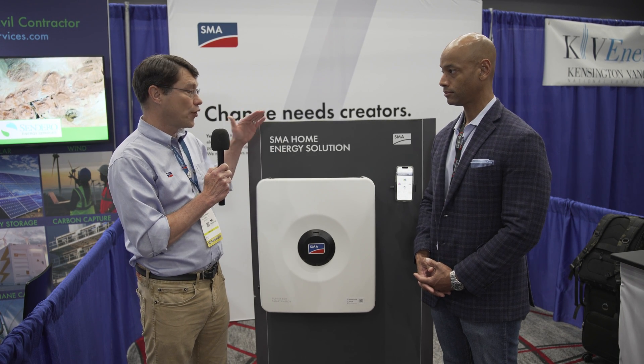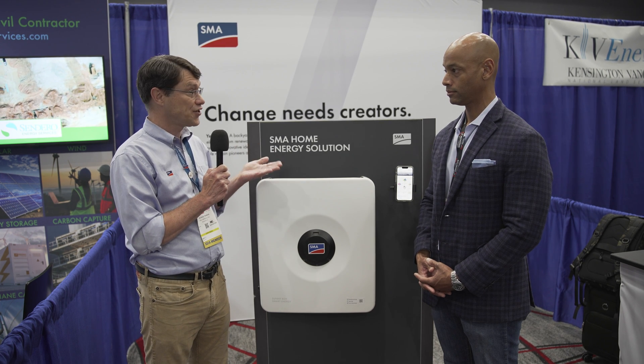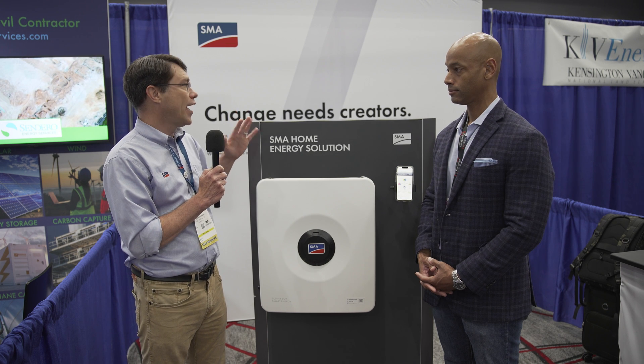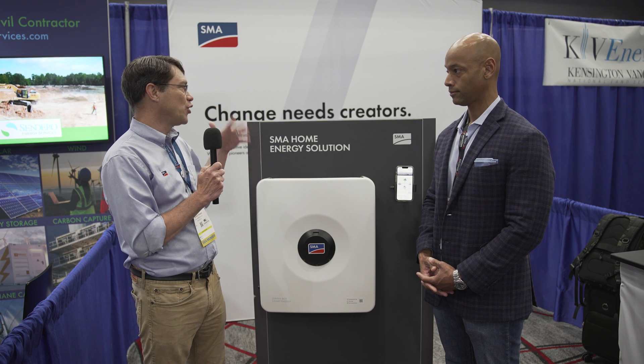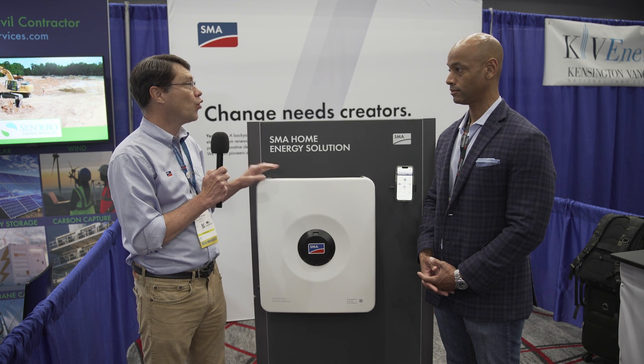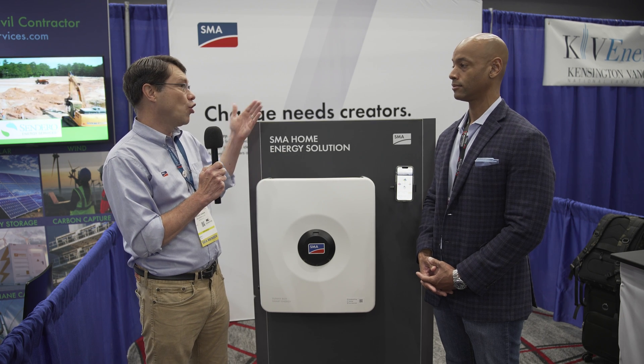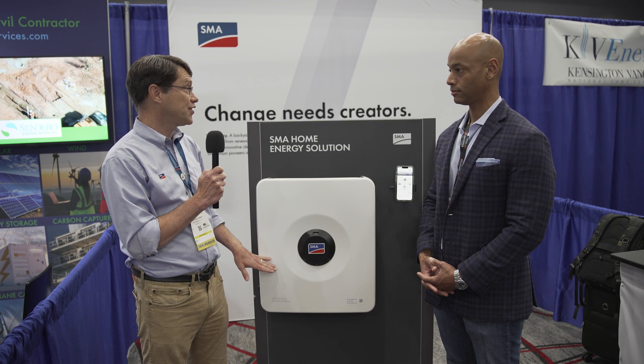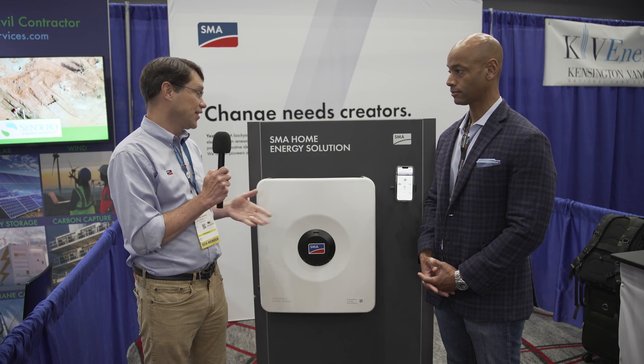SunSpec, the industry organization, certifies receivers that are compliant with their open standard. We at SMA go through an additional level of testing and approval to make sure that while SunSpec-certified rapid shutdown signaling is occurring correctly, our arc fault detection, ground fault detection, shade fix, and power optimization are none of them impacted by that rapid shutdown signaling. There's a list of approved SunSpec certified devices that we can pair with this. Right now for the Sunny Boy Smart Energy, the AP Smart is a single device with an 80-volt limit and a 15-amp current limit — that matches very nicely with our updated 15-amp input limit on the PV side.